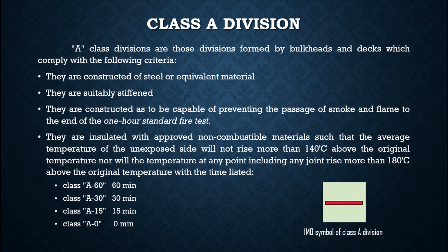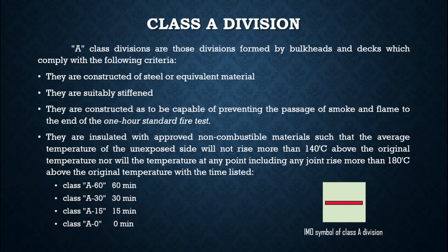Class A divisions are insulated with approved non-combustible material such that the average temperature of the unexposed side will not rise more than 140 degrees Celsius above the original temperature, nor will the temperature at any point including any joint rise more than 180 degrees Celsius above the original temperature. The 140°C is the average temperature of the bulkhead on the unexposed side, while 180°C applies to localized points such as where a stiffener beam is welded, as stiffener beams act as thermal conductors carrying heat from the fire zone.